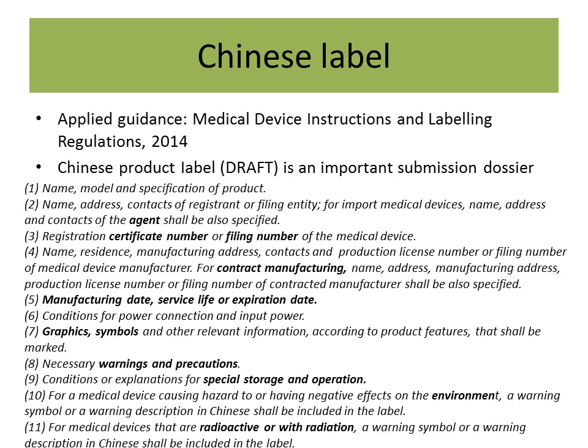Chinese product label is way less strict. You could change the layout after approval because the submitted product label is just a draft. There is no regulation regarding the outer packaging label. We suggest noting the info of certification number and Chinese product name on all selling units so no trouble can be found in supply chain.